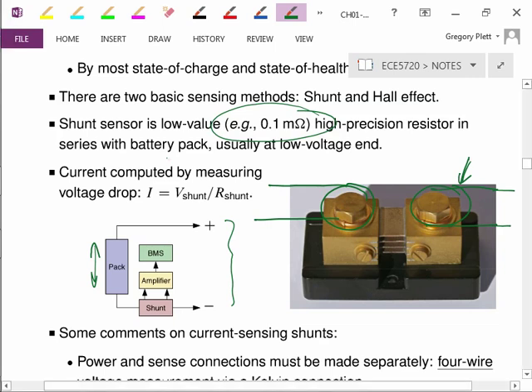So the power lost in the shunt resistor is almost zero. The maximum voltage drop across the resistor is on the order of 50 millivolts maybe. So there's almost no power dissipated, but that voltage drop, that IR drop, is something I can measure with an analog to digital converter, and then I can infer that the pack current is the voltage drop across the shunt divided by the known resistance of the shunt resistor.